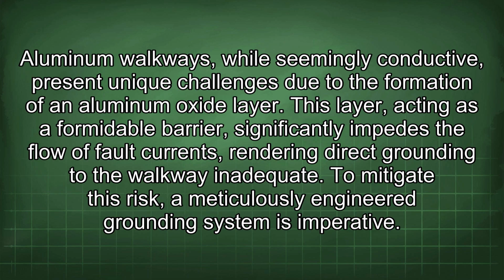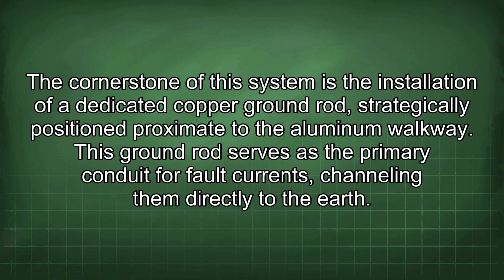Aluminum walkways, while seemingly conductive, present unique challenges due to the formation of an aluminum oxide layer. This layer, acting as a formidable barrier, significantly impedes the flow of fault currents, rendering direct grounding to the walkway inadequate. To mitigate this risk, a meticulously engineered grounding system is imperative. The cornerstone of this system is the installation of a dedicated copper ground rod, strategically positioned proximate to the aluminum walkway. This ground rod serves as the primary conduit for fault currents, channeling them directly to the earth.